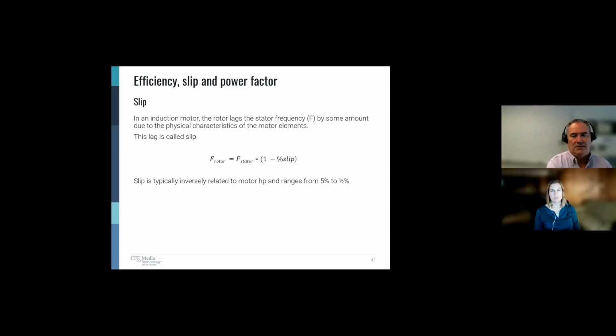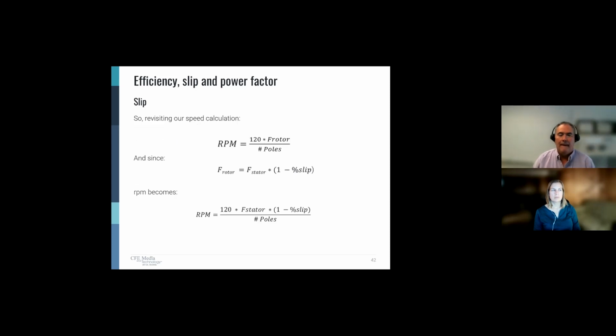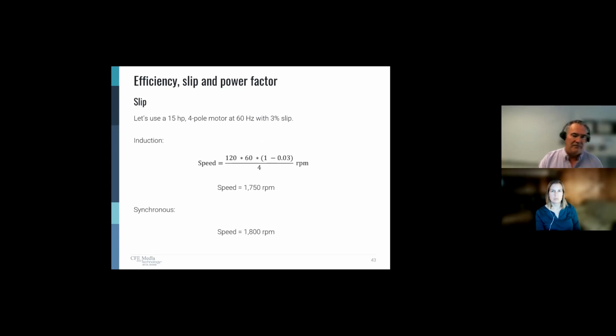The reason we bring this up is it's important, because we look at a motor and we say, oh, that's a 4-pole 60 hertz motor, it's going to run at 1800 RPM. No, it's really not. And this is why. When we revisit that calculation, we have to account for the slip. The calculation used to be 120 times the frequency divided by the number of poles. Now when we add the slip into this calculation, we have to modify our numerator, which changes our RPM. So a 15 horsepower, 4-pole motor, 60 hertz, 3% slip doesn't run at 1800 RPM anymore.